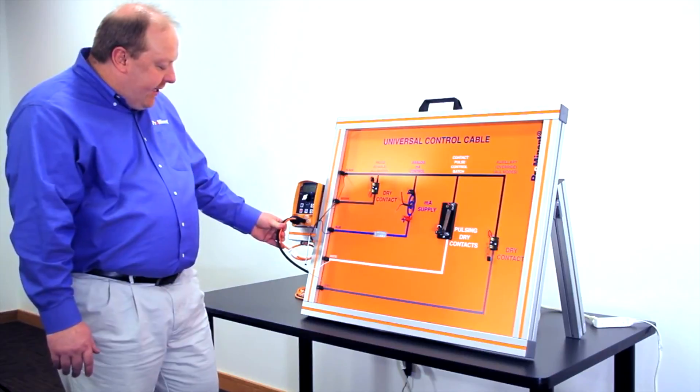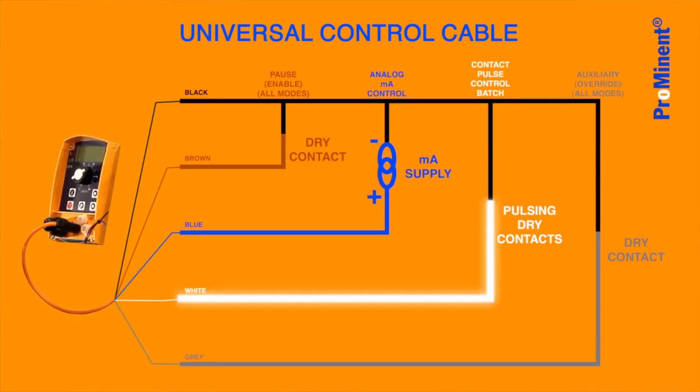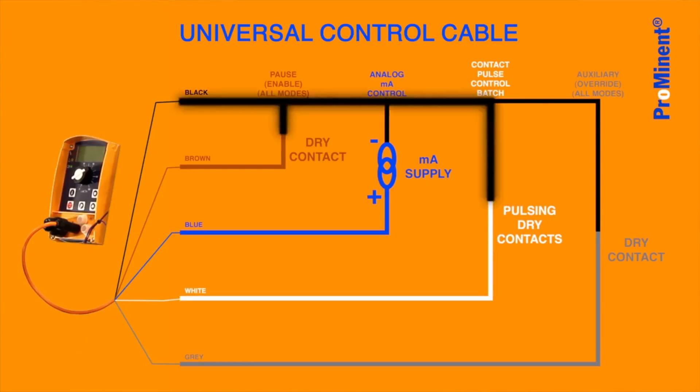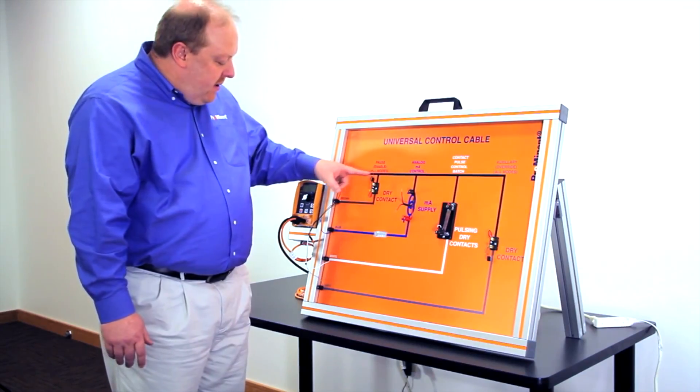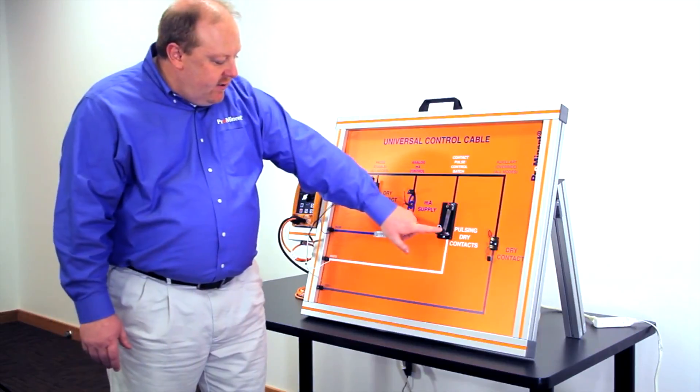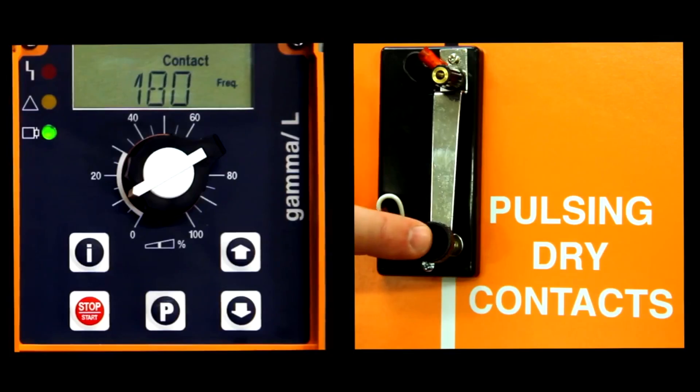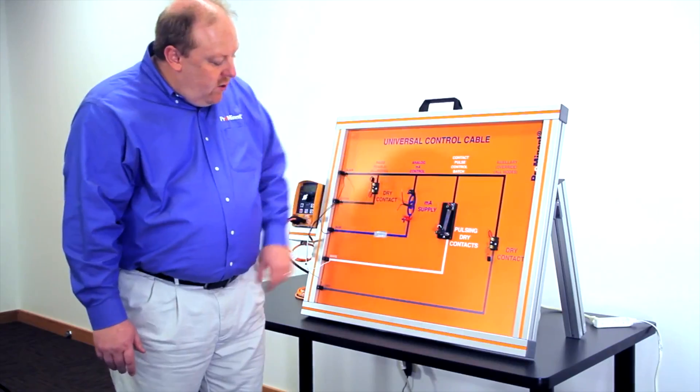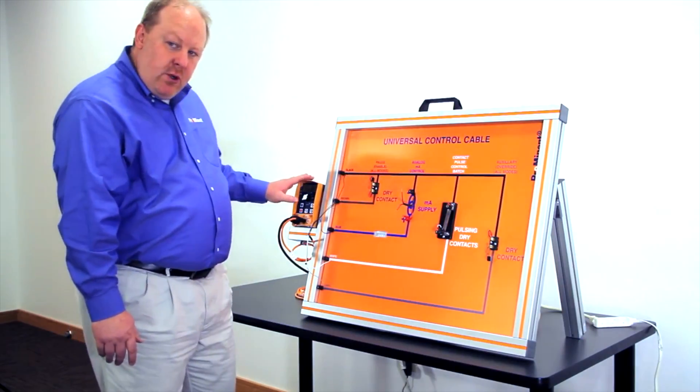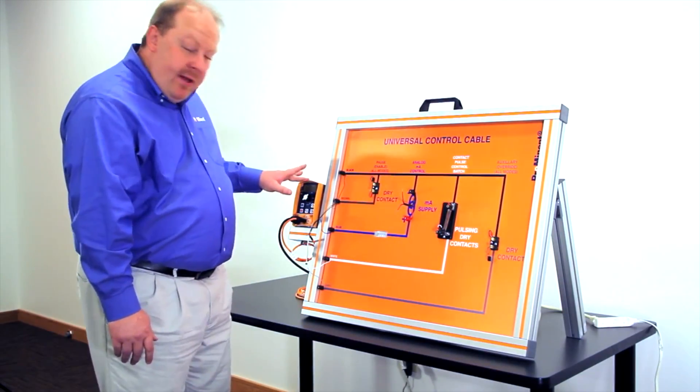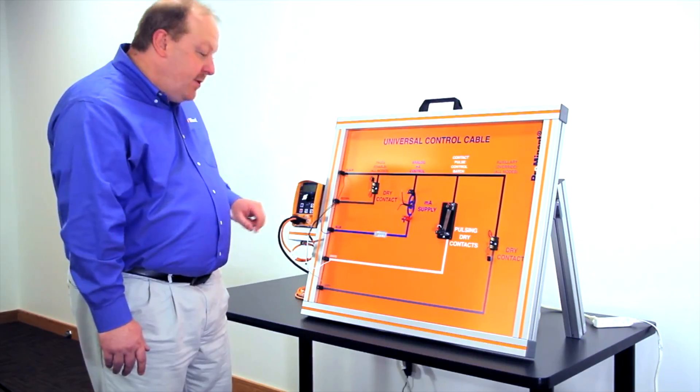To initiate the contact mode of operation, we need the white wire to short to the black wire, which is in contact again with the brown wire. That's our pause function. Every time we press this button, it's going to short our white wire to that black wire, which is contacted to the brown wire. One contact in, the pump strokes one time. We can manipulate that ratio with other options on the pump.